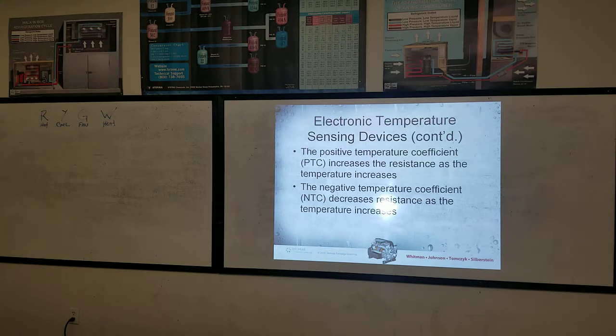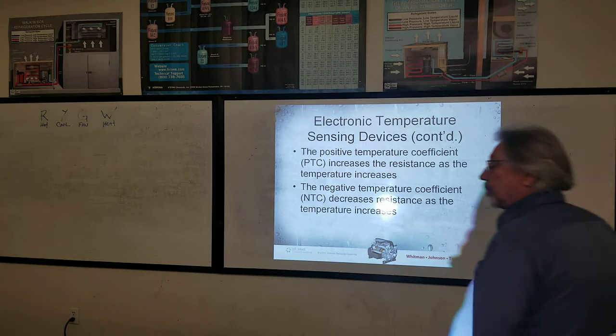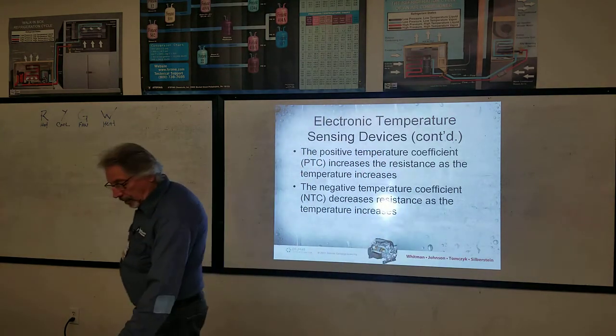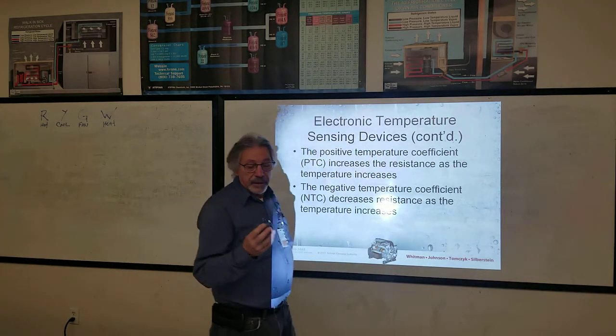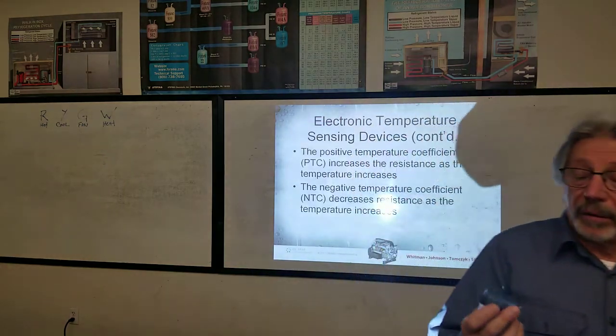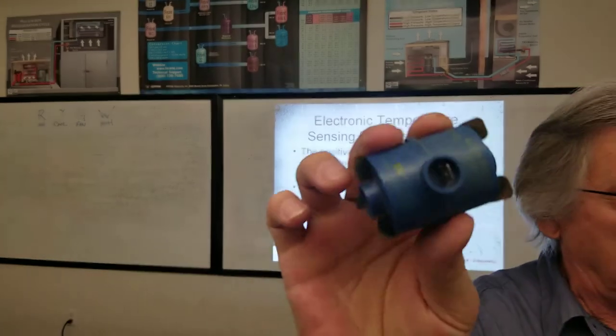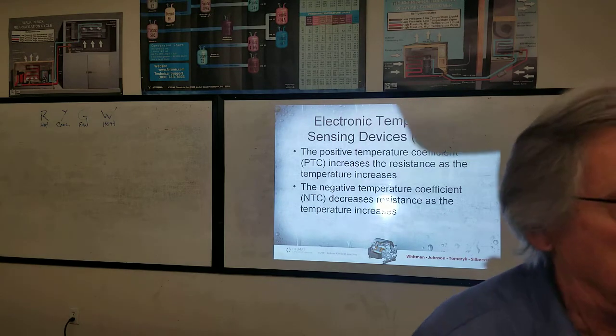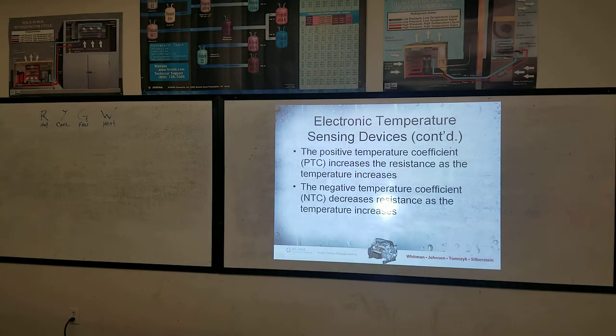Oh. So you can touch that. Here's another example of a thermistor. It's one of these. This is called a Sarek. As it says Sarek on it. That's Spock's father. This is used for starting compressors. As the current goes through it, it heats it up, and it makes so much resistance in that control that no current can go through it.